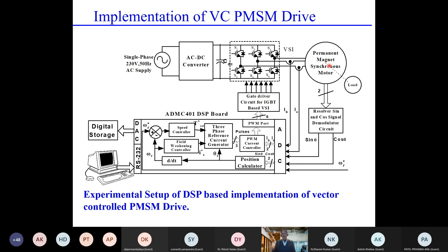These are some results for a prototype 2 kilowatt Parker Hannifin motor. In the subsequent diagram, left side is the simulation result, right side is the experimental result. This step is the reference speed, and the ramp is the actual speed. The next two waveforms are phase B and phase C current. They are on the same scale, where one division is 275 radians per second for speed, and one division is equal to 5 amperes for current.